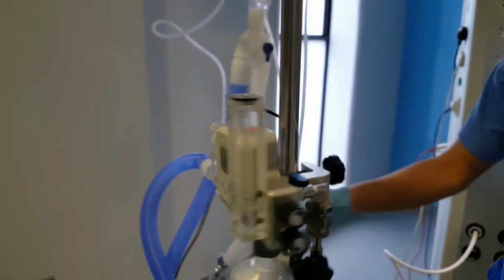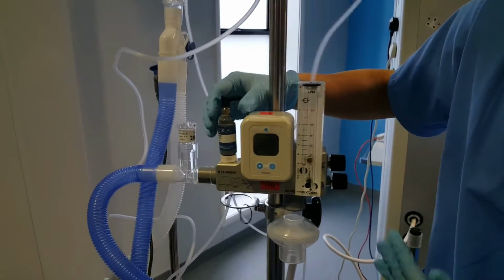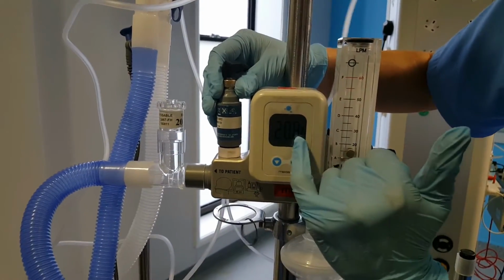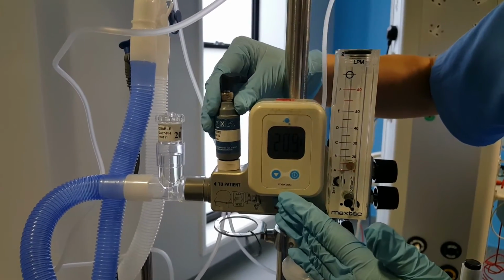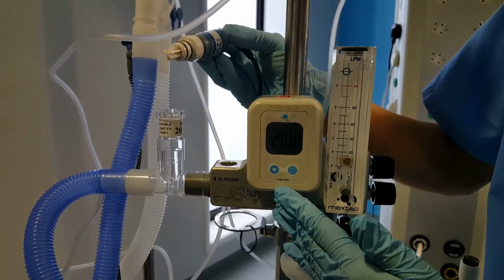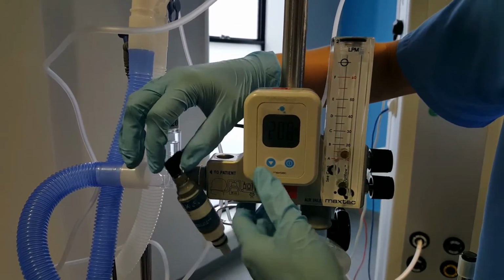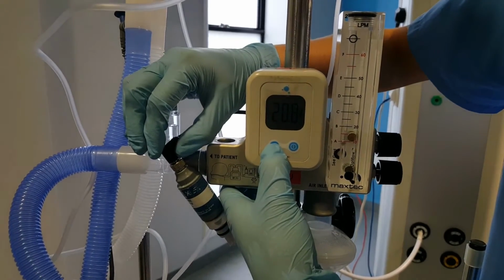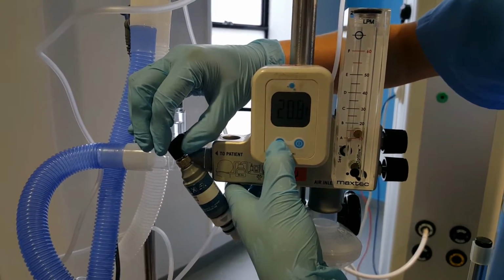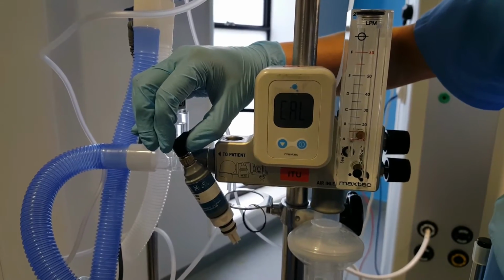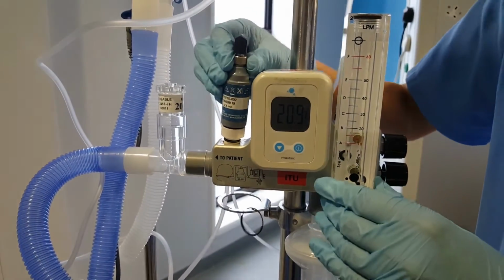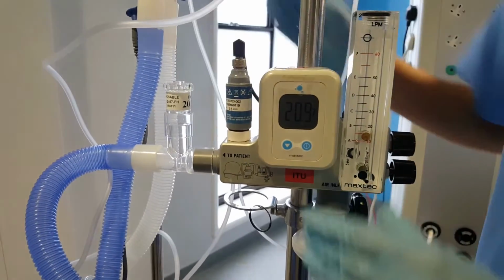So what you do is you calibrate it to room air. So I know it says 20.8 at the minute, but we will recalibrate it. So you take this part out, and you can just leave it hanging there. Keep your finger just on the arrow, and it will calibrate. So that's it. And then it will say 20.9. So you know that it is calibrated to room air. And you put it back in.